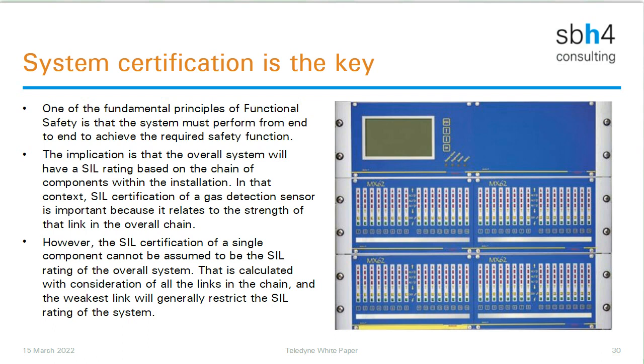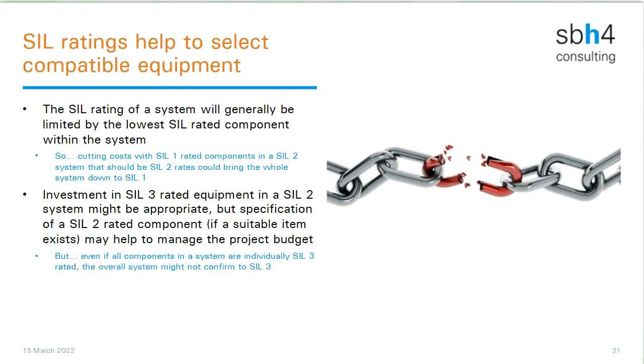The overall system can be thought of as a sum of the component parts. Having said that, the safety integrity level of a total system can never really be better than the safety integrity level of any one particular component within that system. So if our requirement is that the system operates at SIL 2, safety integrity level 2, then we will definitely need individual components within that system to be at safety integrity level 2, or perhaps better. Because as we put more and more components together and build more complicated systems, then the overall probability of failure of that system becomes higher. And therefore it may be necessary to have certain pieces of individual equipment within a system rated at SIL level 3 in order for the total system to have a SIL level of 2.